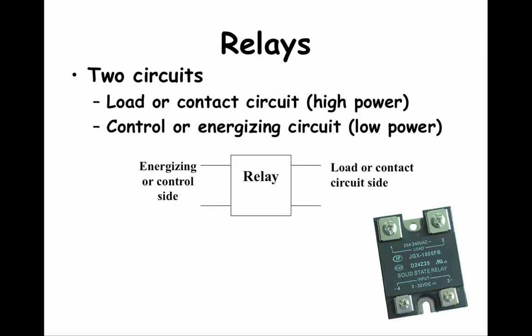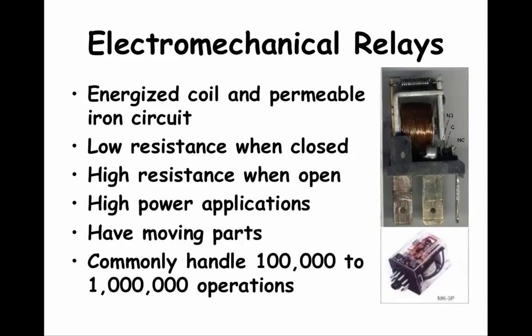The relay shown here is a solid state relay. Solid state relays do not have moving parts. This slide shows some electromechanical relays. The term electromechanical means that there are moving parts that are moved by the application of an energizing circuit. Electromechanical relays have a coil with a permeable iron circuit that, when energized, moves an armature that opens and closes a circuit.